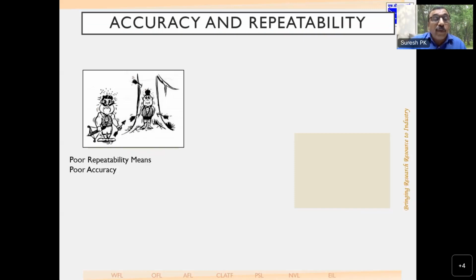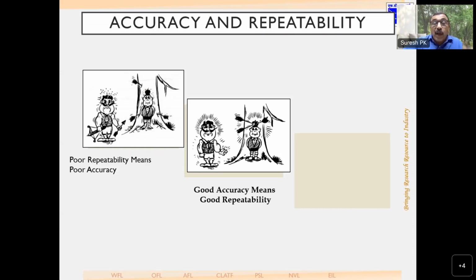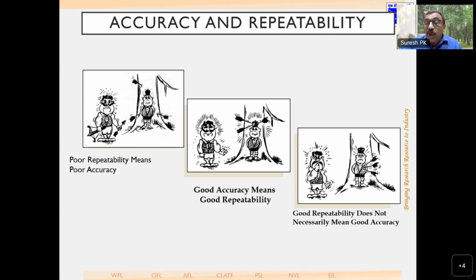Now, if you make a measurement and you are getting poor repeatability, it always means poor accuracy. You are never getting an accurate measurement. But good accuracy always comes with good repeatability, while good repeatability does not necessarily mean good accuracy. It may be that you are consistently getting a wrong reading and you think that it is correct. That is the most dangerous part of it. Good repeatability is not an indication of good accuracy.